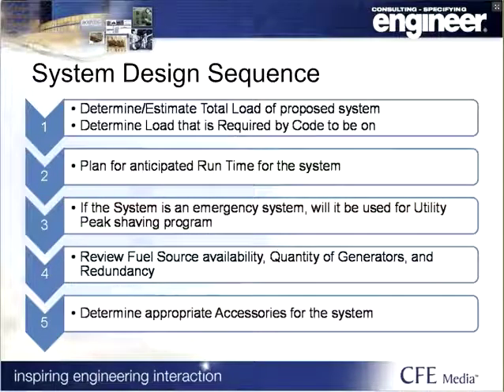If the system is an emergency system, whether or not it's going to be used for a utility peak shaving program, and that would be like a generator demand response program, that's certainly a consideration up front, because it will affect what kind of generators you're using and will affect your installation.